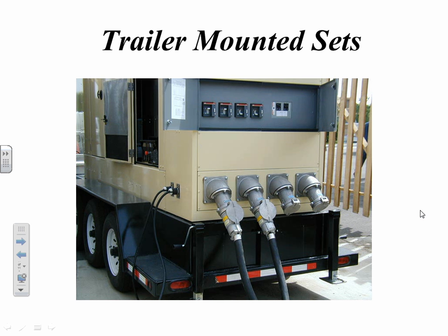But it's not a parallel delta, like technically the one I showed you earlier was really a 240, 480, because it had 2 coils in series. But it's a parallel set of coils for 120, 240, and the bottom one is the center tap for the 120. No, you can do it. But I thought I was going to be buying a transformer for this one. I studied what I saw when I was at the site. There was a little diagram. And they had like a little link bar here for each leg.